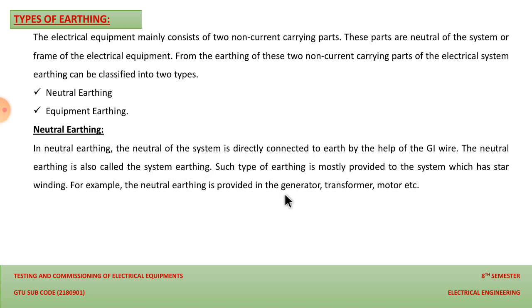Why is it called system earthing? Because it is a type of earthing which is mostly provided to a system which has a star winding. For example, neutral earthing is provided to the generator, transformer and motor. Basically we have star and delta winding for such equipment. Whenever there is a star connection in the equipment, we can easily take out the neutral from the star connection. That neutral wire is connected with the earth with GI wire. So it is the earthing of the whole system. That is why it is called system earthing.